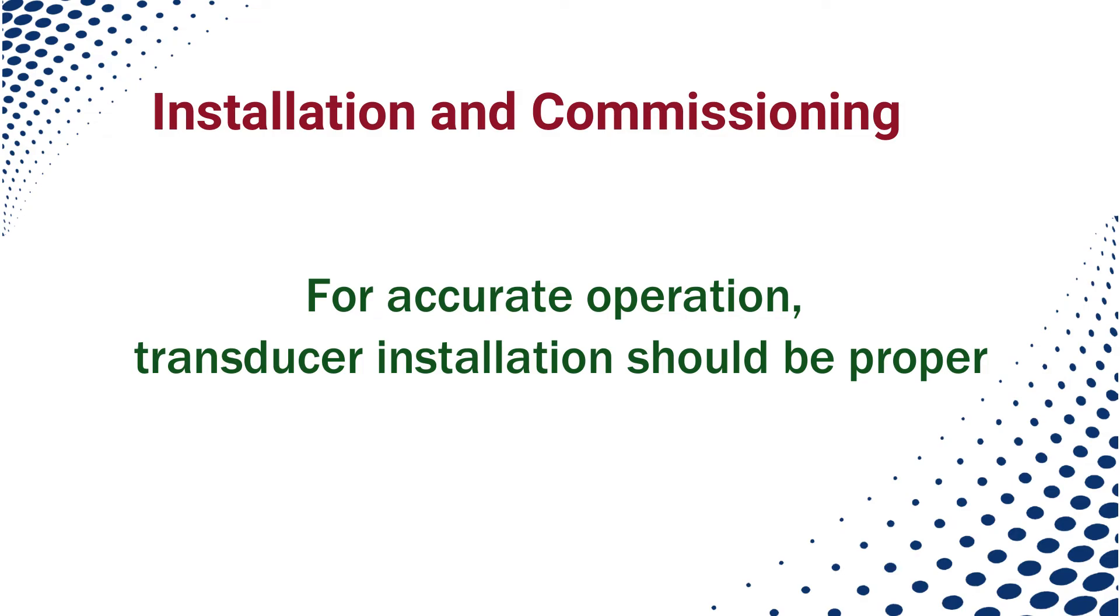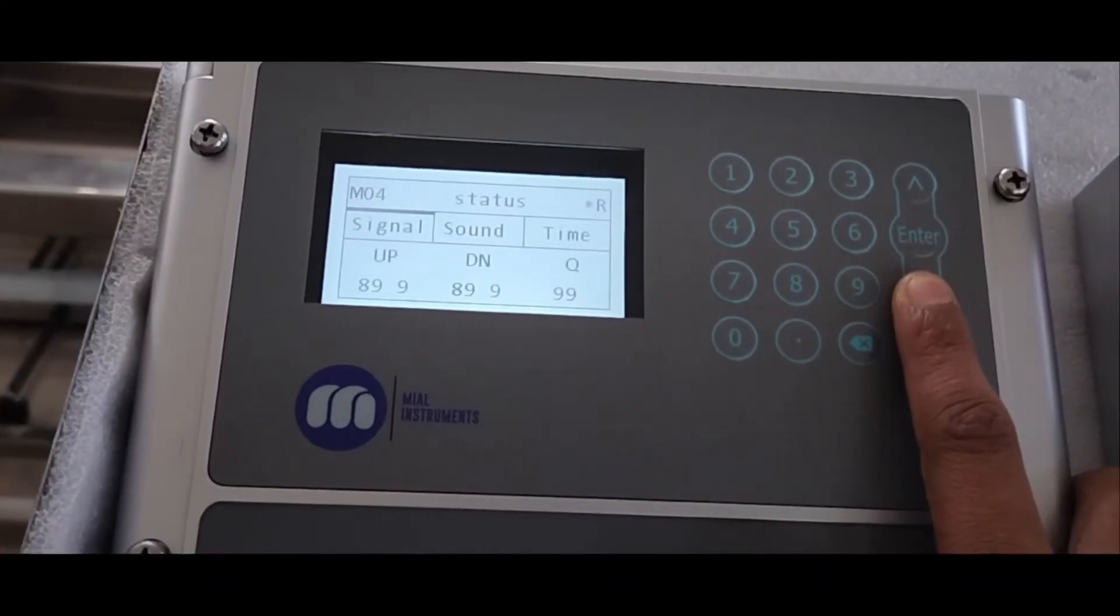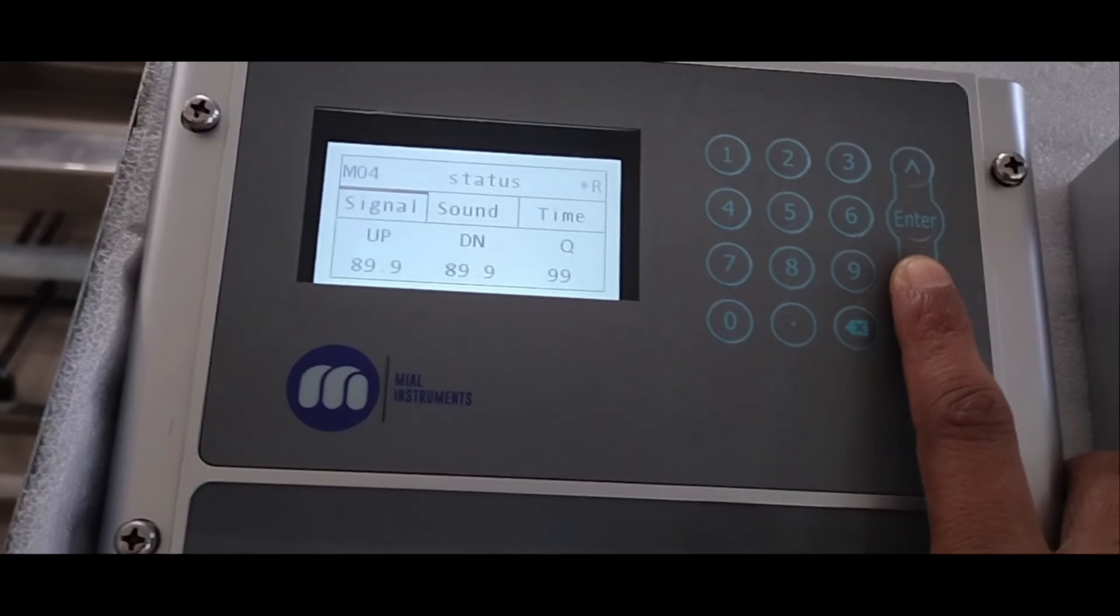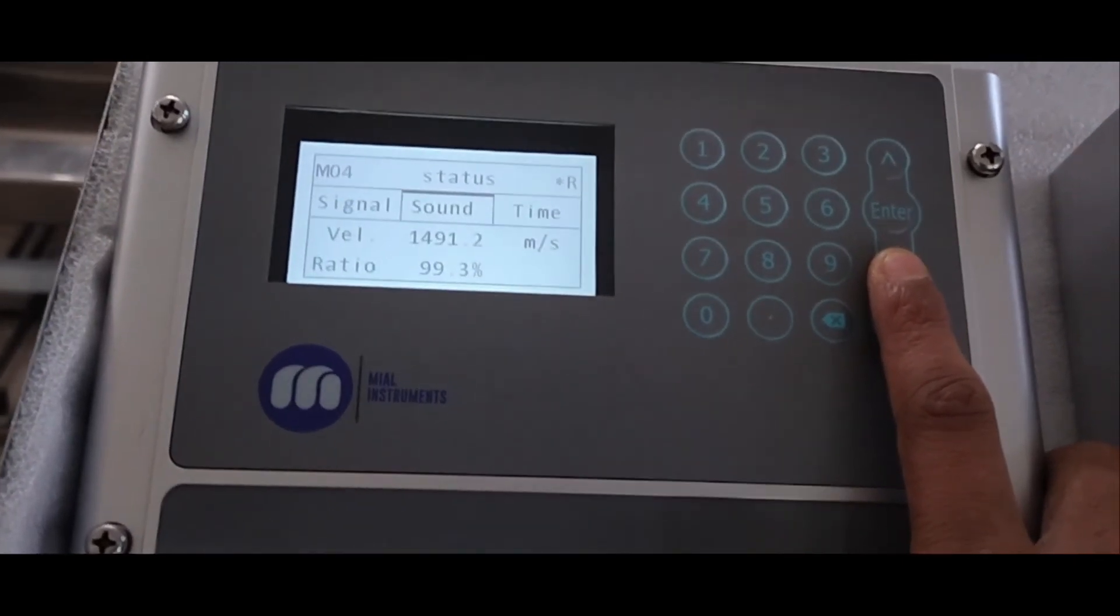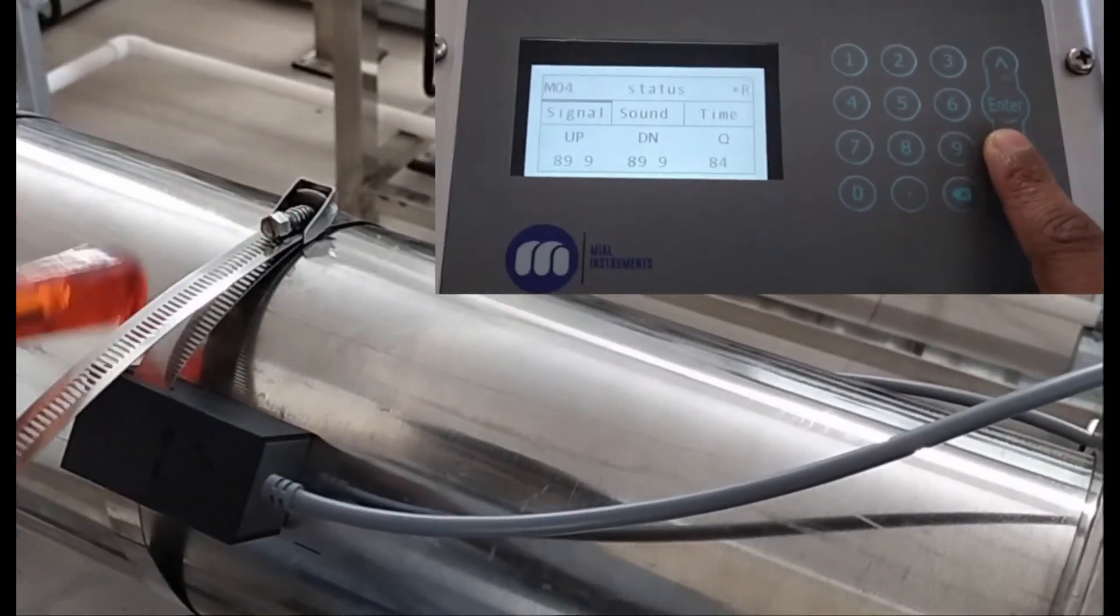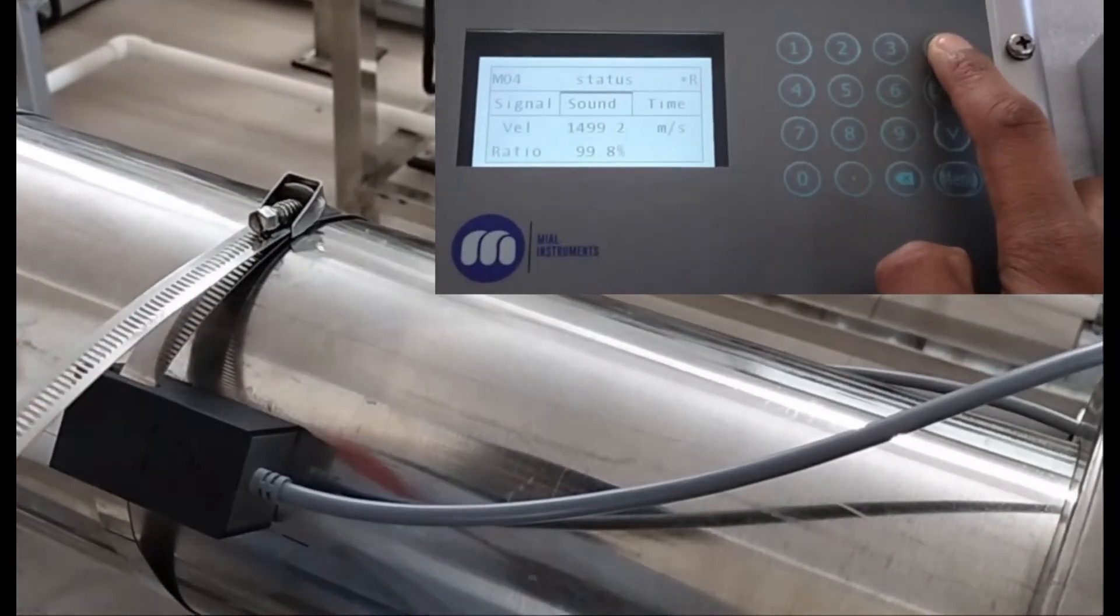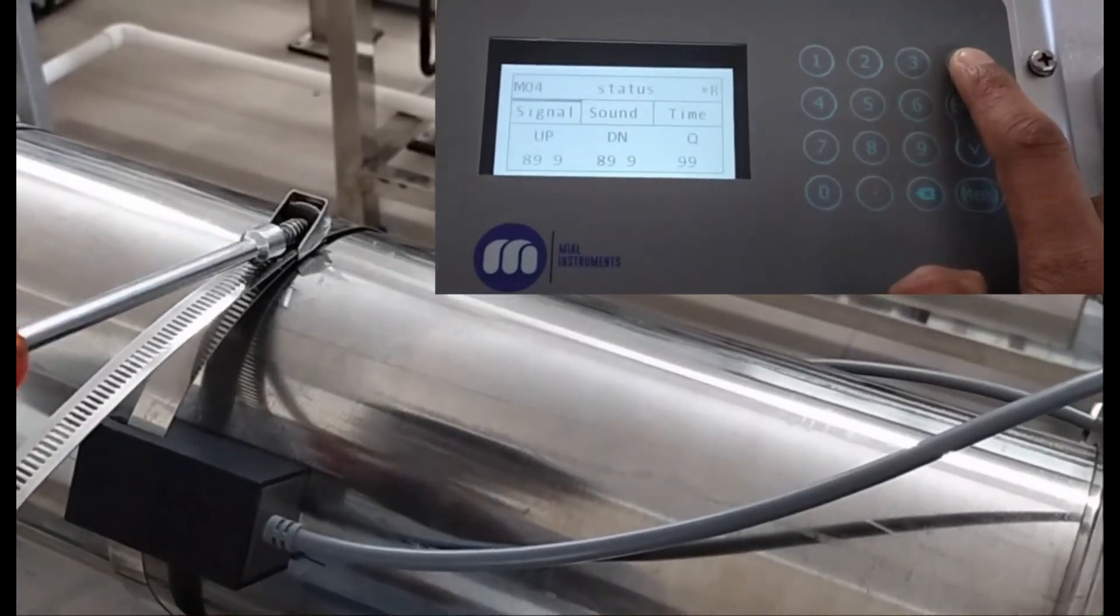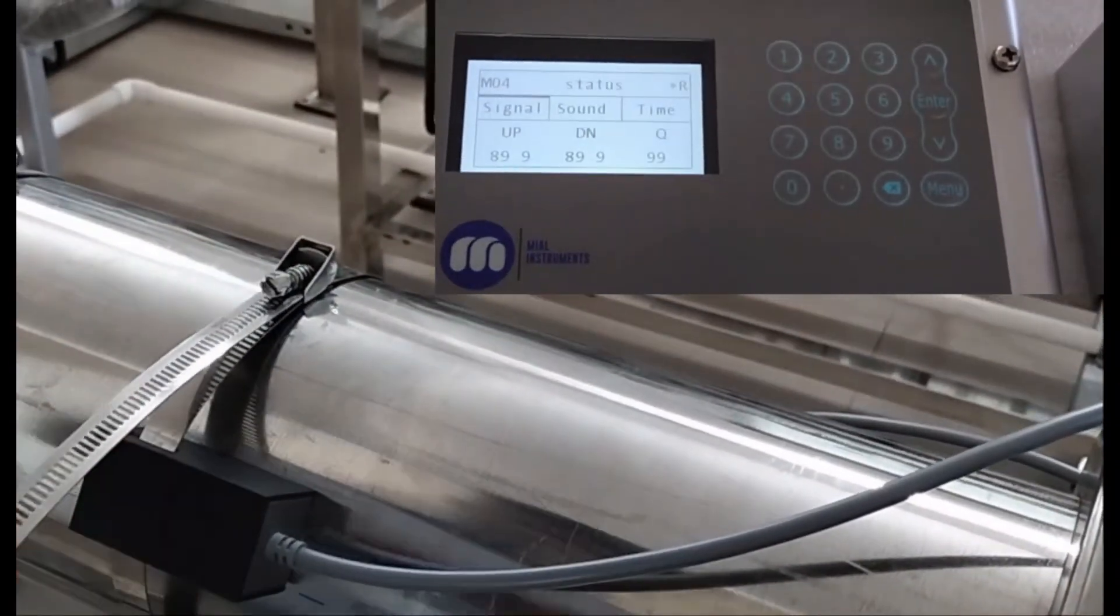First, switch on the power supply and energize the meter display. Then press the down button just below the enter button and go to menu 04. Q value is short for signal quality. It varies from 0 to 99. 99 represents the maximum signal quality. In the next tab, just press the down button. The ratio is the transit time ratio and it should be 100 percent. To get the mentioned values, adjust one of the sensors as shown in the video. Tighten the pipe strap after attaining the desired values. Thank you.